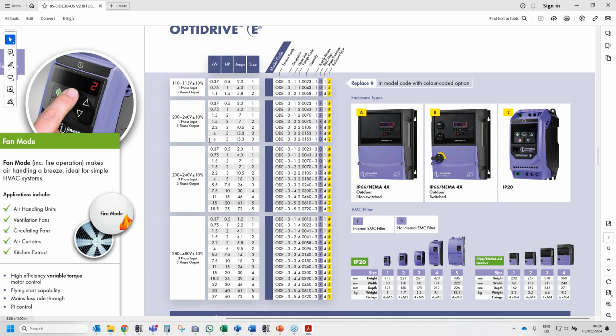If it's bigger than this, say in some countries they do have like a 480 volt single phase, we can use a 3-phase 480 volt drive, but we derate it by 50%. So it's possible to do that, and we actually have an application note to give you the details on that if you need to do that. But single phase to 3-phase, it's not a problem on 200 volt or the 220 volt.